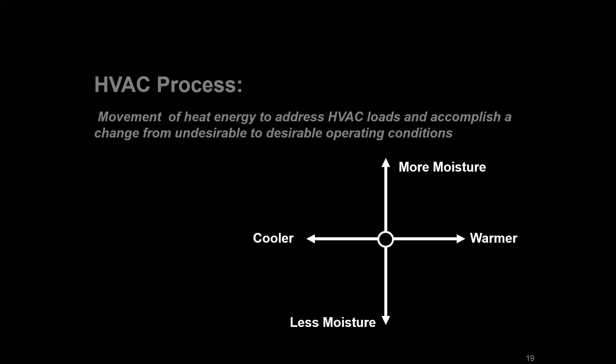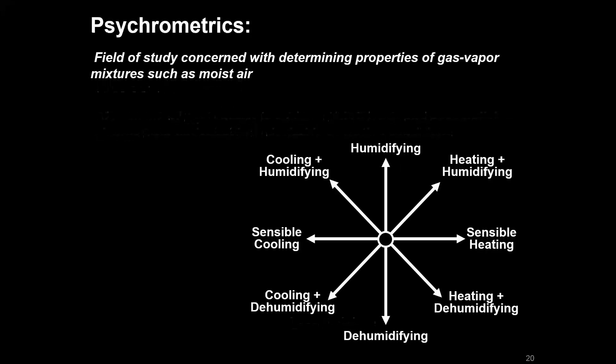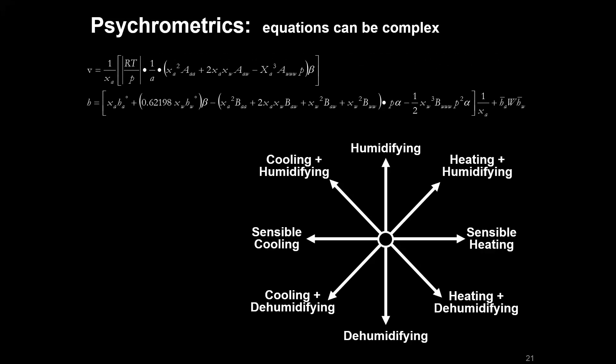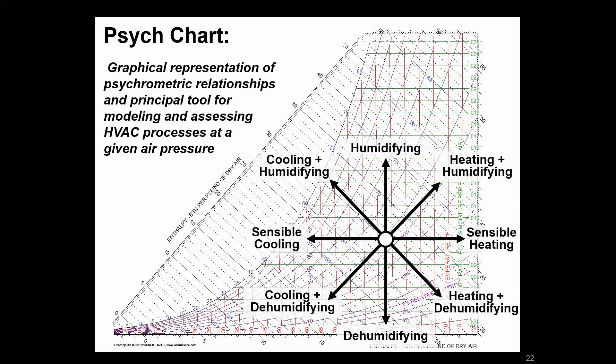Now, we're using terms like more moist, less moist, warmer, cooler air. But when we talk about looking at air for the purposes of RCX, we're going to use the more industry-common terms of humidifying, dehumidifying, sensible heating, cooling, and then the various combinations. This is governed by the field of psychrometrics, which looks at the properties of air. The equations in that field can be quite complex, but luckily we have a tool called the psychrometric chart, or psych chart, which is a graphical representation of those relationships. This is really going to be the primary tool we use to quickly assess an HVAC system looking at loads associated with the air.